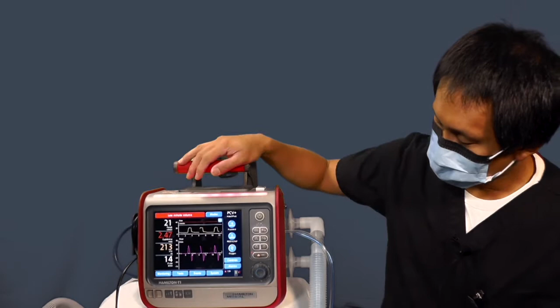So that's the alarm sound that you'll hear unless you hit the alarm silence button or fix the issue. Okay. Probably one of the first things you'll want to do after you start the patient on the ventilator is adjust your alarms. So you'll notice you've got flashing lights. It'll be either red or this yellow-orange color, and also a corresponding message on the front of the screen to tell you what alarm it is.